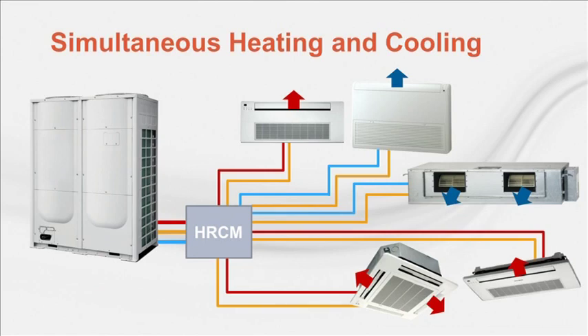The heat recovery control module can also route refrigerant from one indoor unit to another, bypassing the outdoor unit. This works by transferring energy between indoor units that are working in opposing modes. The setup proves to be really flexible. As you may have noticed in these diagrams, there are many styles of indoor unit that can be selected for a specific application, and they usually range from a cooling capacity of several MBH to a few tons. Often, many different configurations are available.